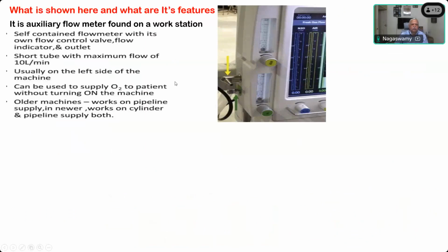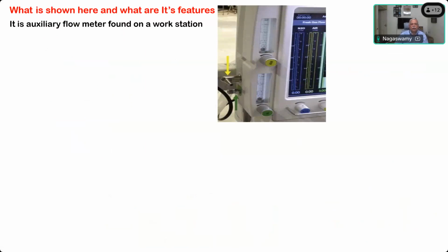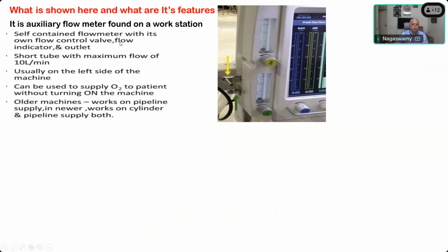So what are the features of that? It works even when the machine is on or the machine is off, like the oxygen flush. So it can work even when the machine is not on. Maximum flow is up to 10 liters per minute. It is a self-contained flow meter with its own flow control valve, flow indicator and outlet. Short tube with a maximum flow of 10 liters per minute.